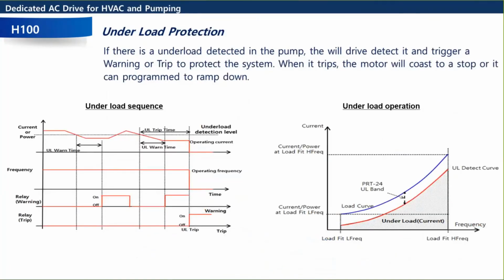Under load protection is something that's going to work best if you do that load tuning that we just mentioned. Under load would be used to trigger a trip or a warning. The difference between a trip and a warning is that a warning keeps running, but just flashes on the keypad, underload, underload, underload. Whereas a trip will flash underload and it'll stop you. That's the difference between the two. You can set the trip to coast to stop, or you could set it to a ramp to stop, following your deceleration rate.